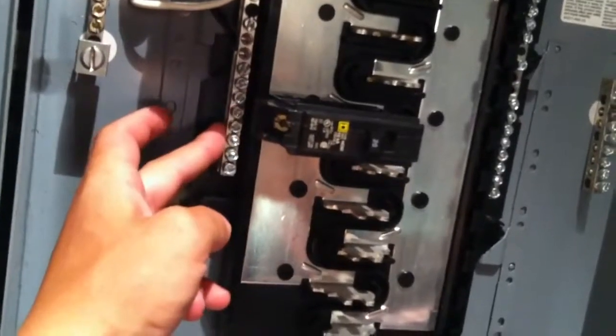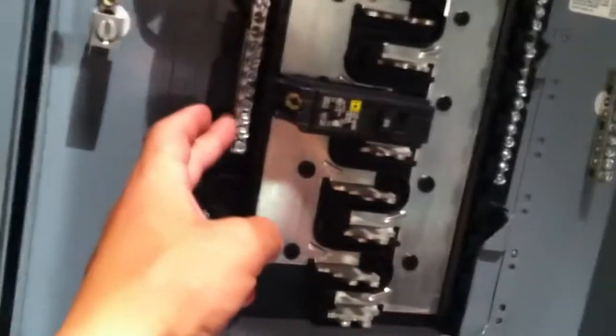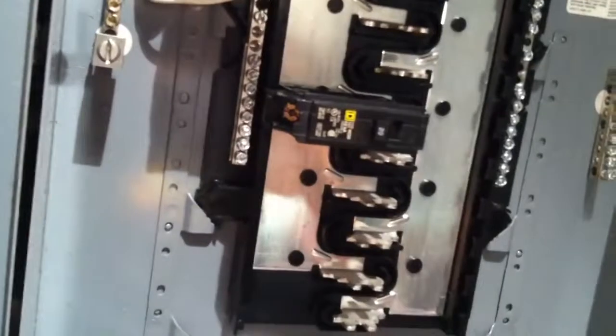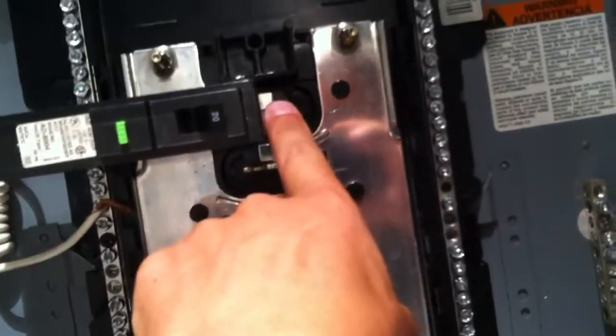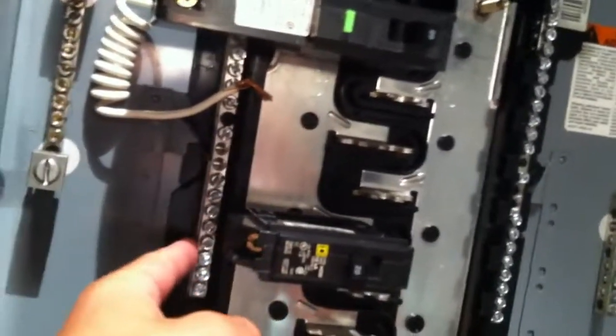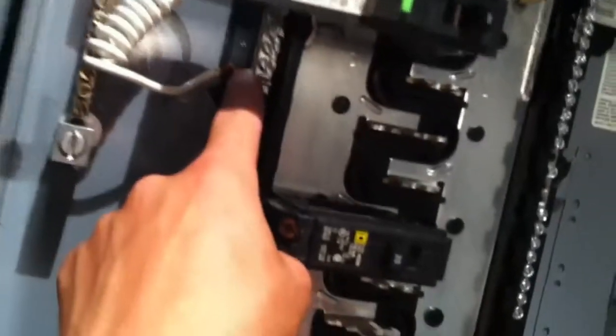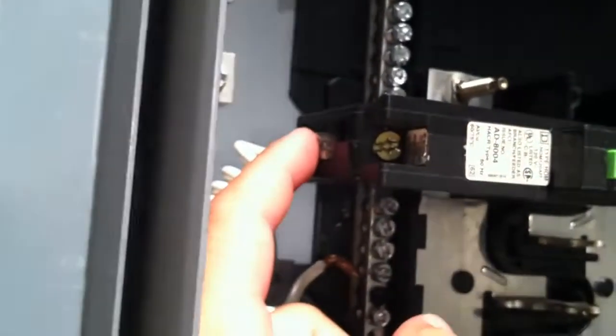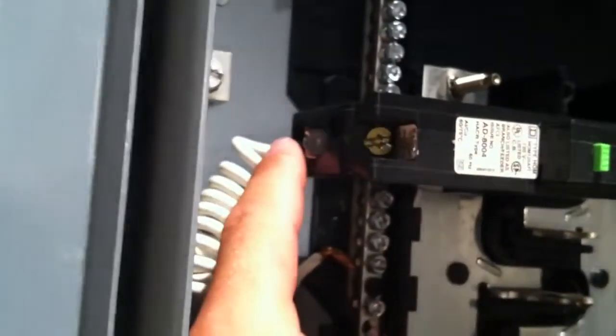Okay, normally you have it pulling from the hotline. There's your output hotline, and then you have your neutral coming off your little neutral bar here, your screw terminal. So you have your screw terminal that goes to your circuit, then you have your hot that comes out of your breaker, and that goes to your circuit. Okay. In this case, same thing. It pulls from the hotline. You have your hot that goes to your circuit, but you do not pull from this neutral screw terminal directly. You go through the circuit breaker. So the circuit breaker has this wire coming out of it, and that pulls from this neutral screw terminal. And you can see that on the output of the breaker, there's also a silver screw. So there's a silver screw and a gold screw. Okay, and the gold screw is your hot, the silver is your neutral.